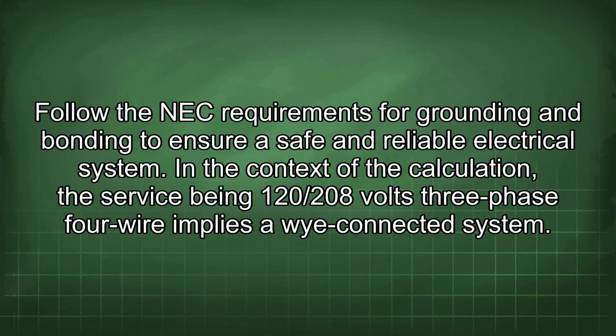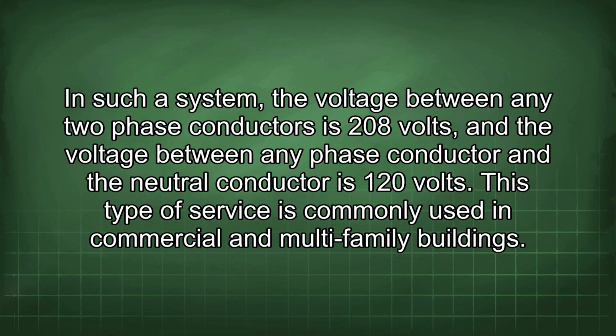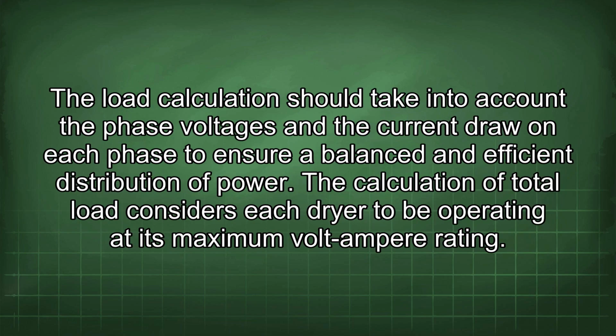In the context of the calculation, the service being 120/208 volts 3-phase 4-wire implies a Y-connected system. In such a system, the voltage between any two-phase conductors is 208 volts, and the voltage between any phase conductor and the neutral conductor is 120 volts. This type of service is commonly used in commercial and multi-family buildings. The load calculation should take into account the phase voltages and the current draw on each phase to ensure a balanced and efficient distribution of power.